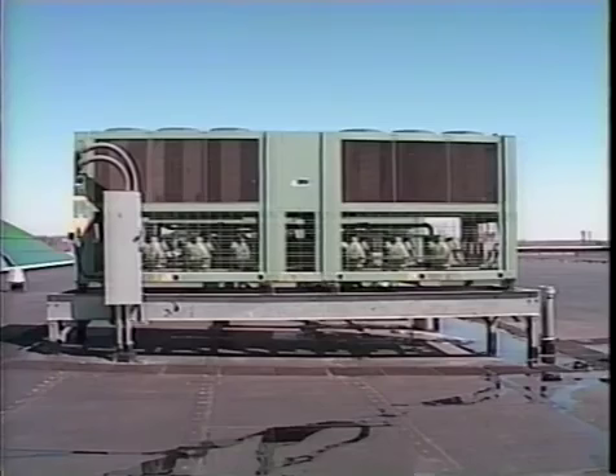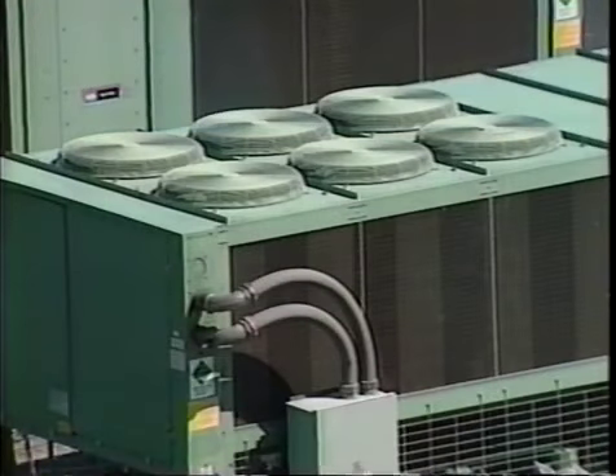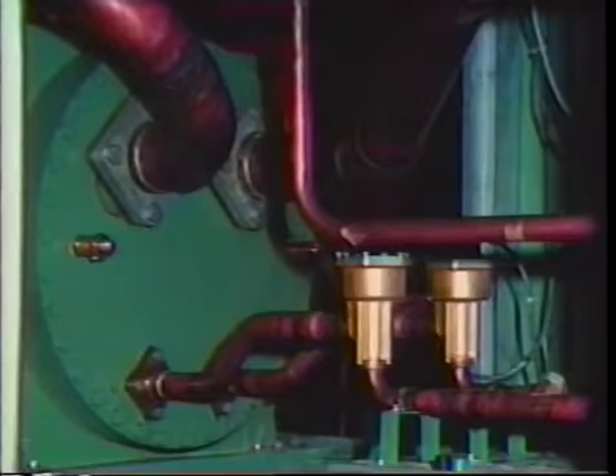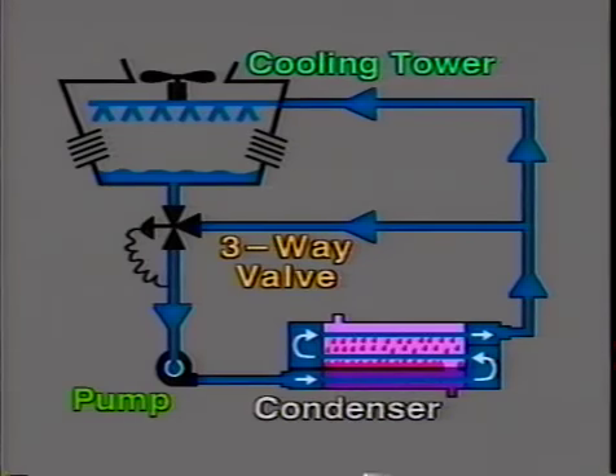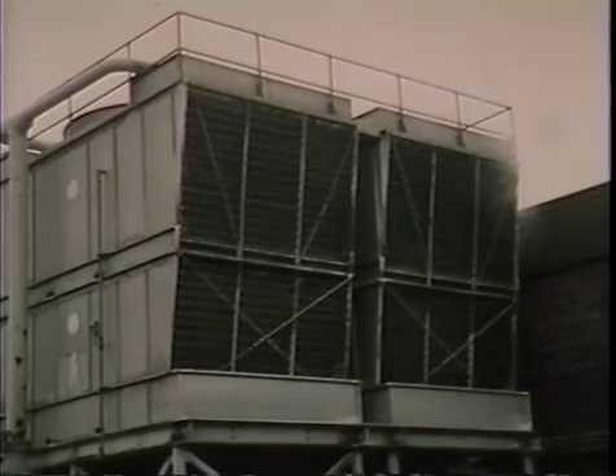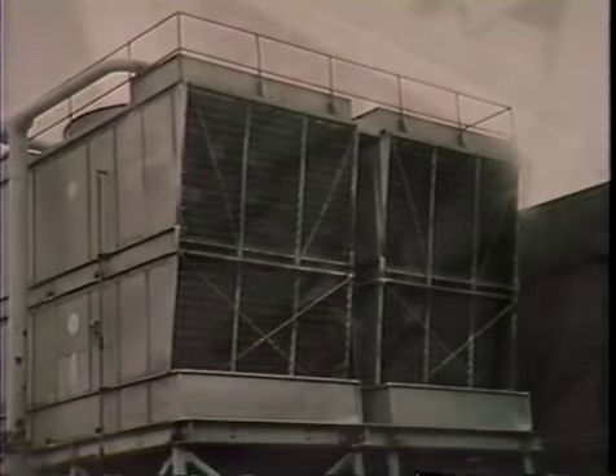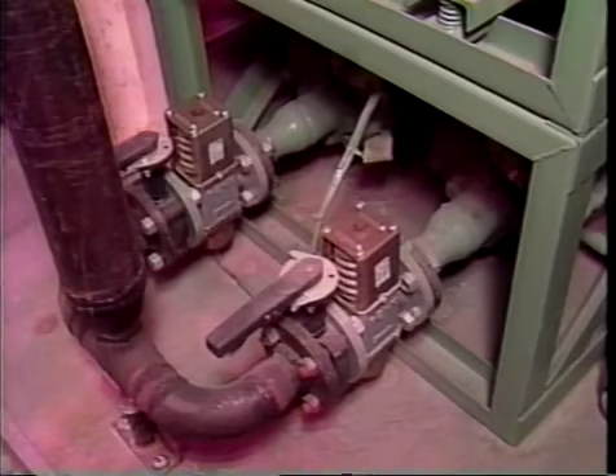The condenser fans may be cycled by head pressure controls or by air temperature controls so as to maintain sufficient head pressure to adequately feed the expansion valve when air temperatures drop below the desirable operating range. Even water-cooled condensers may require head pressure control if the condenser water drops below 70 degrees Fahrenheit. One way of keeping the head pressure up is to allow some of the water to bypass around the cooling tower, therefore reducing the heat removed at the tower. Another way is to cycle the cooling tower fans just as you would the fans on an air-cooled condenser. Using water-regulating valves is yet another way to provide the required condensing head pressure to adequately feed the expansion valve.